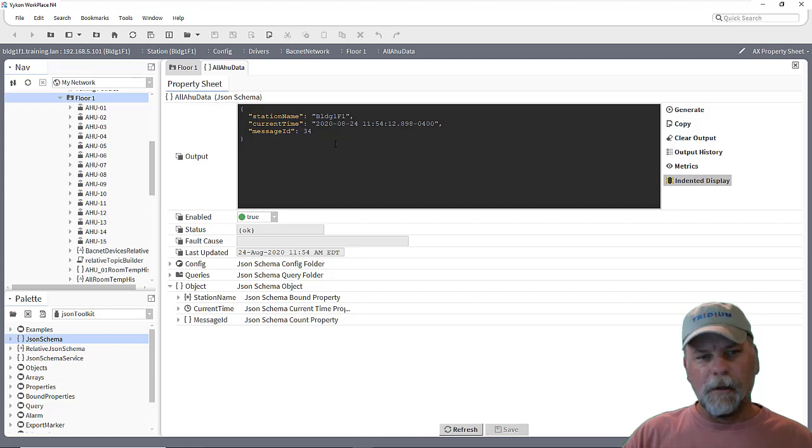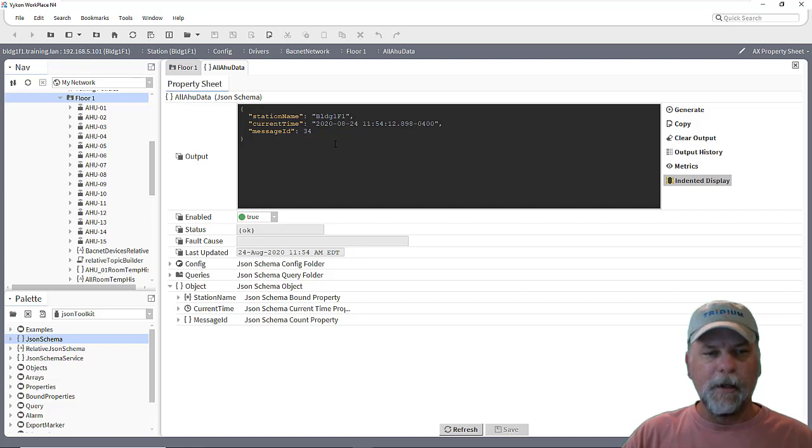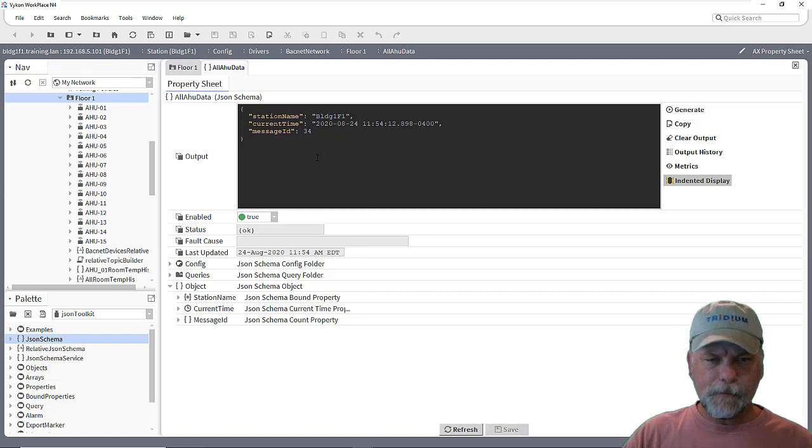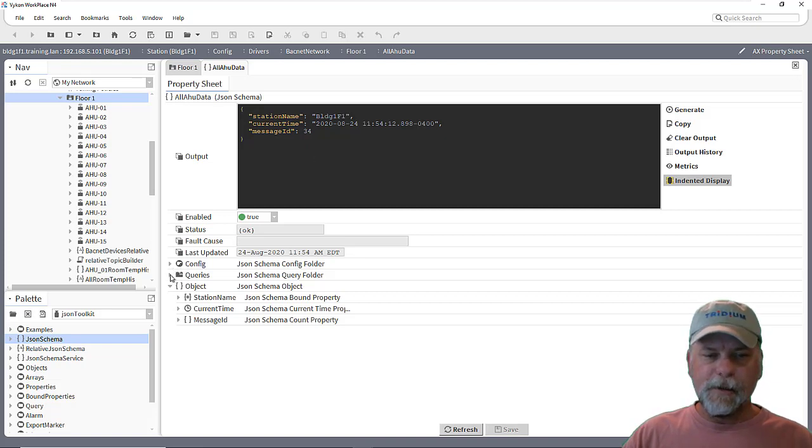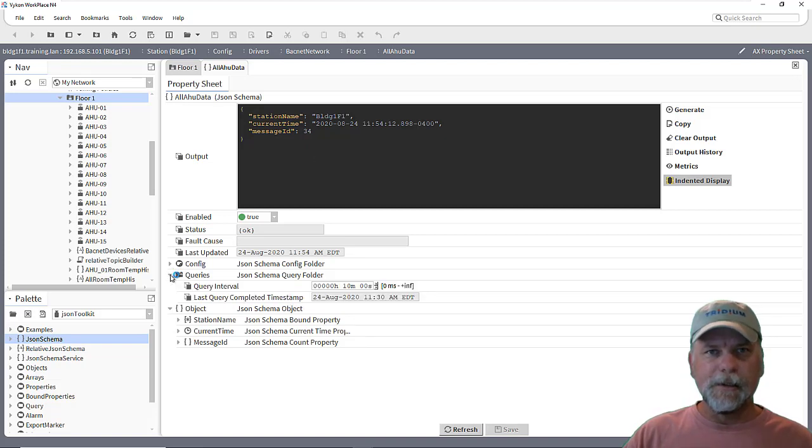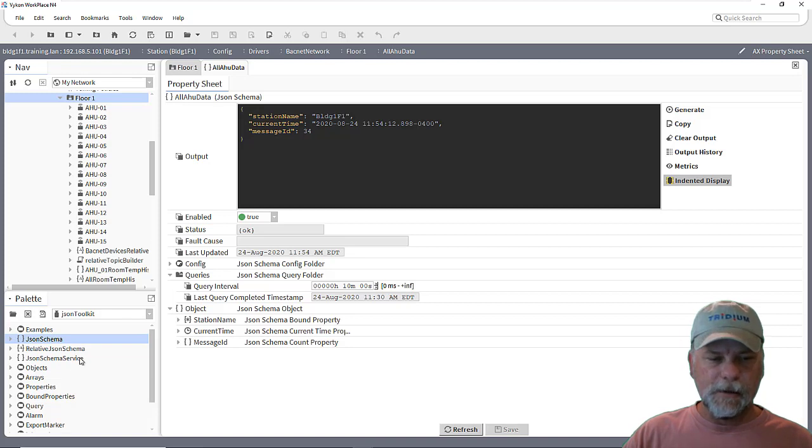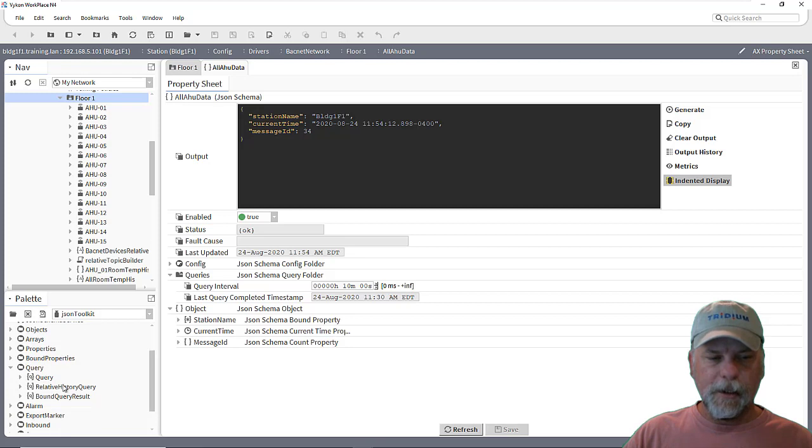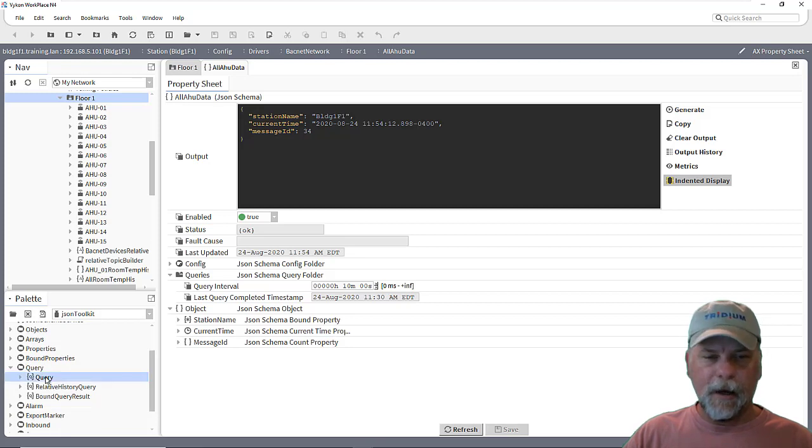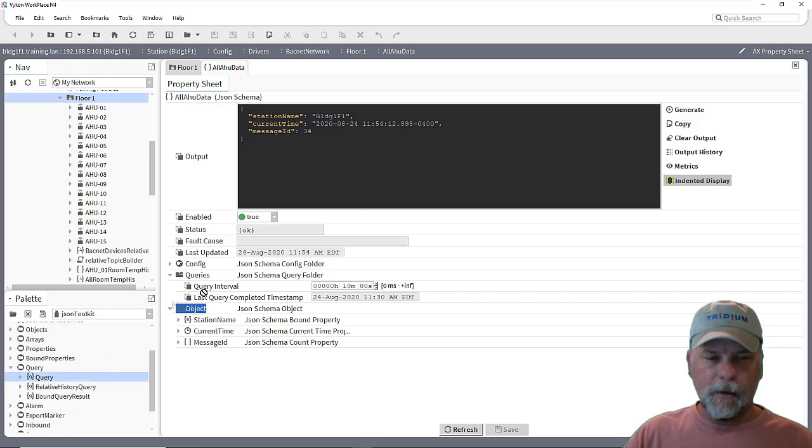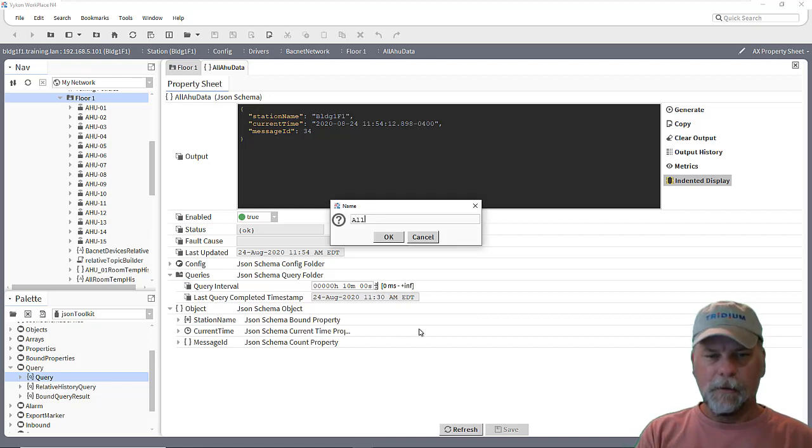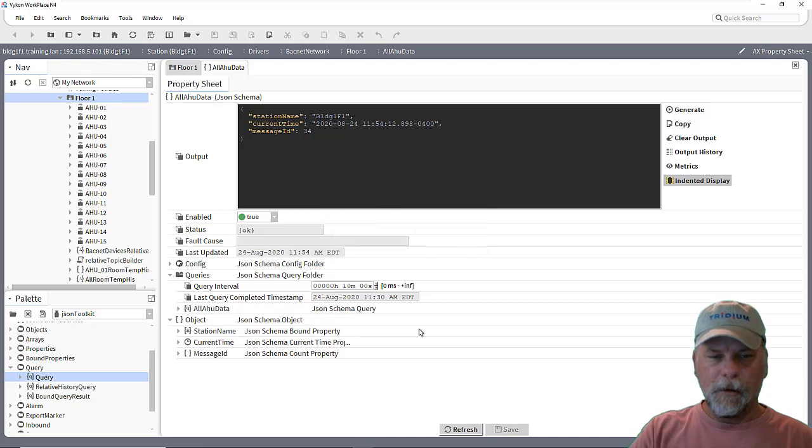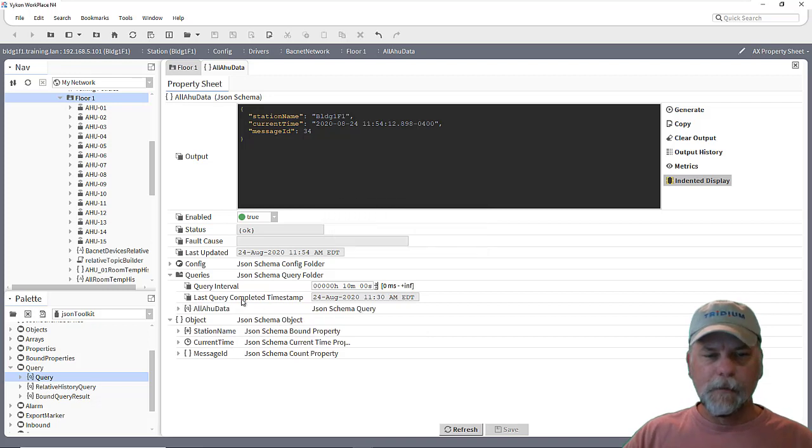But I want to actually include real-time point data, maybe from the air handlers. So the way that we would go about doing that, one option anyway, is to use this queries component of the JSON schema. And in the JSON toolkit, there's a query subfolder here. And we can click and drag out a query from the palette. And maybe I'll just call this all AHU data or something along those lines.